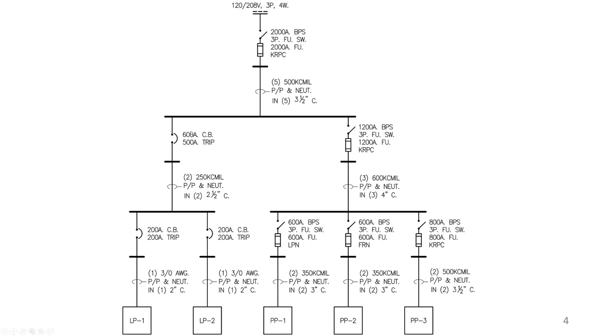Now, if I'm going over to the other side where I'm showing, for example, these circuit breakers, I have a 500 being fed from a 2000. I have no problem with selective coordination there. But when I go from a 500 to a 200, most likely you will not be selectively coordinated. On the other hand, I may not care about having selective coordination. So you have to either follow the electrical code that governs the area where the job is and figure out, do I need selective coordination for that? Depends on what it feeds. Or do I care about selective coordination?